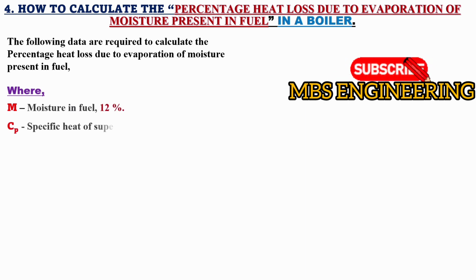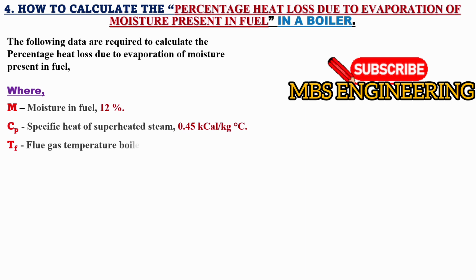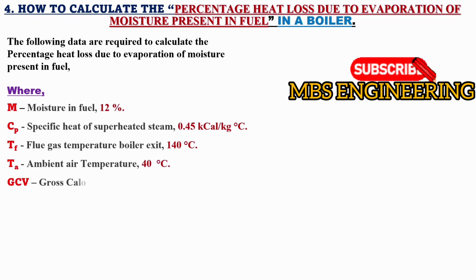Cp is the specific heat of superheated steam, 0.45 kilocalories per kilogram degree Celsius. Tf is the flue gas temperature at boiler exit, 140 degrees Celsius. Ta is the ambient air temperature, 40 degrees Celsius. GCV is the gross calorific value of fuel, 3500 kilocalories per kilogram.